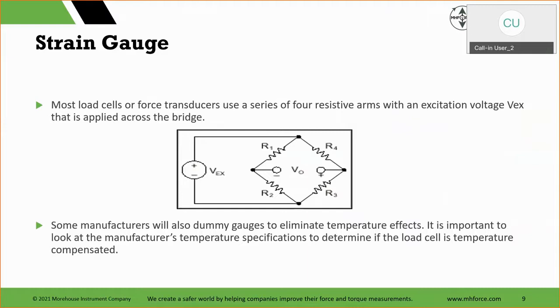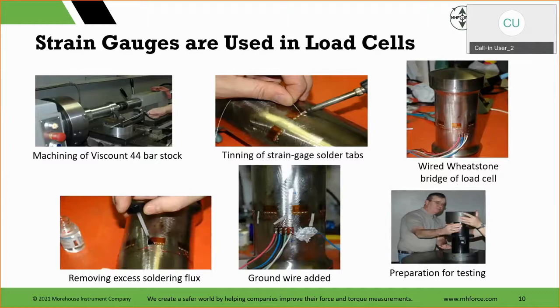And that's one thing we see a lot of, where manufacturers may not have temperature compensated their load cells. This is another thing, not in this course, but I'm just adding a little bit to it. If you were ever curious about that, in the dead of winter, if you're not in the South, you could take a load cell into the lab before you warm it up, test it, see what it reads cold, acclimate it for a day or two, and test it again. If you're not getting close to the same readings, it more than likely isn't temperature compensated. So that's a quick way to check.